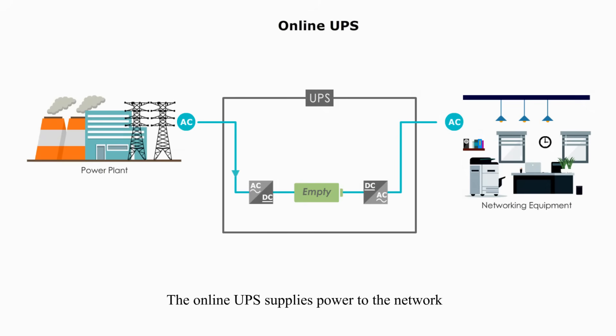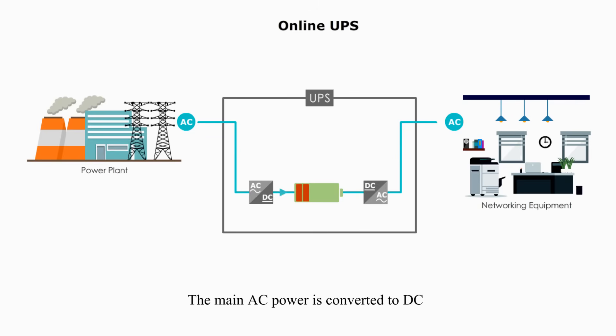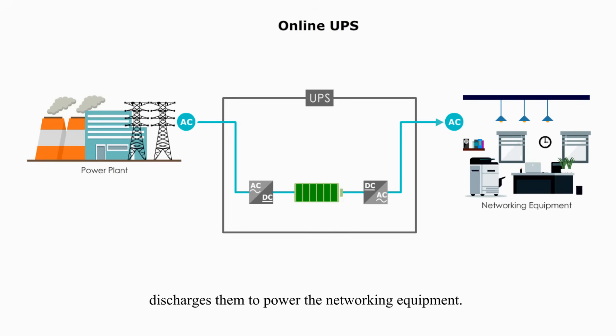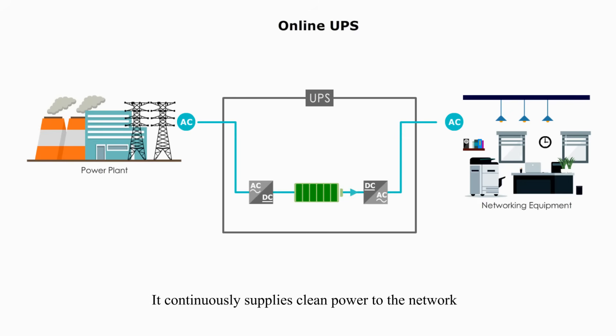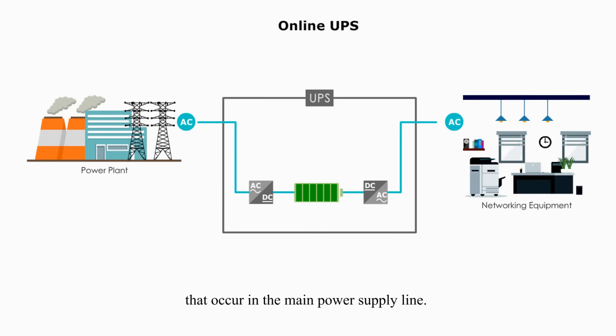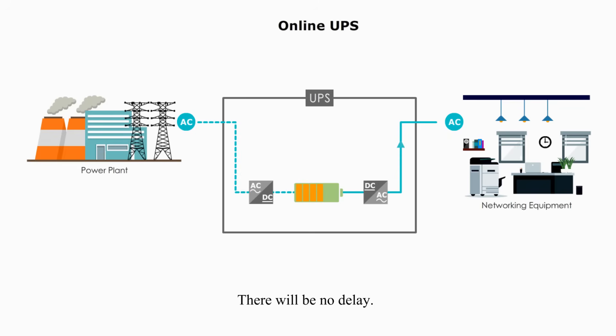The online UPS supplies power to the network from the batteries at all times. The main AC power is converted to DC, which first charges the batteries and then discharges them to power the networking equipment. The online UPS does not require a switching mechanism. It continuously supplies clean power to the network, regardless of power quality problems in the main supply line. Whenever there is a blackout, the battery continues to supply voltage to the network — there will be no delay.